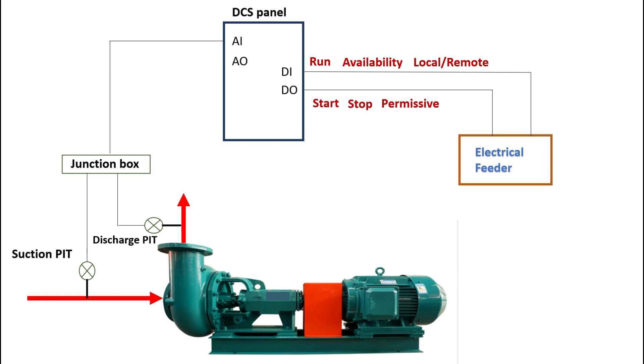Next we have digital output signals — those signals are start command, stop command, and permissive signals to start the motor. These are the basic control supply signals running between the DCS panel and the electrical feeder. From the electrical feeder, all these signals are processed and the main power supply goes to the motor, driving it and making the pump run.